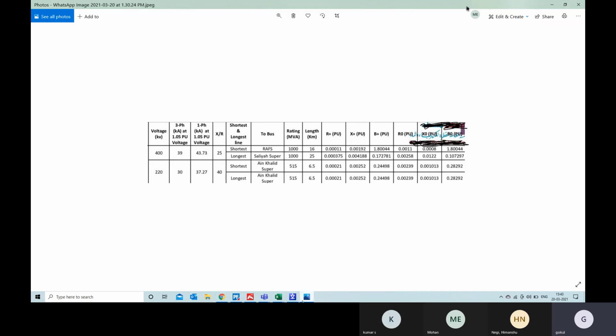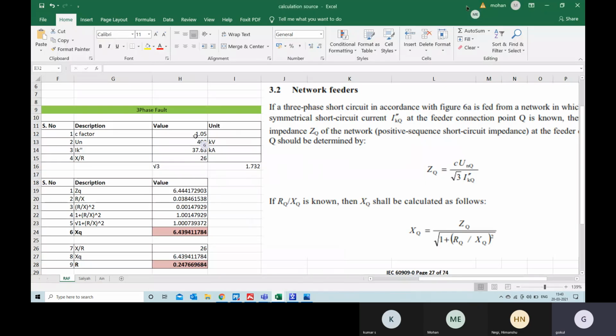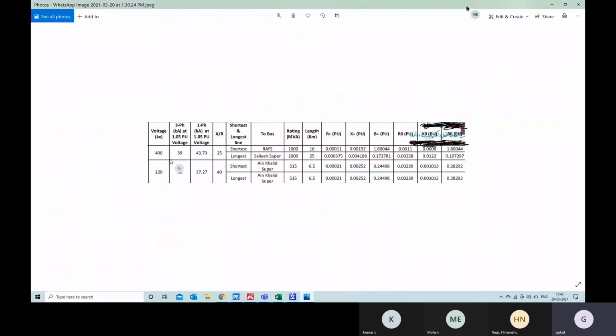So this is exactly what I have used in our calculation: the C factor as 1.05. Un is the nominal system voltage, 400 kV. Then I double dash, as I said, is the symmetrical fault current, and that is 37.63. This is the RAF sheet, the first sheet. So I have taken 37.63 from it.